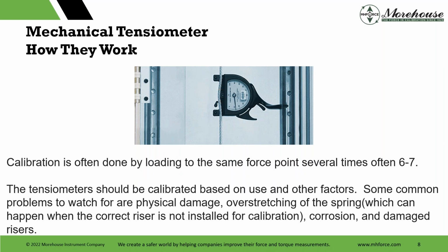Typically, from what I've seen, now we don't calibrate tensiometers. We make equipment to calibrate tensiometers. We don't do it in-house. We could. We just never got into it. We have all the cables. We have everything else. Maybe we should do it. Calibration is often done by loading the same force point several times. I've seen 6 to 7, sometimes I've seen 5. Minimum is at least 3. And you need multiple readings because they don't really repeat as well as you would think for the coarse resolution. And they should be calibrated based on use and other factors.